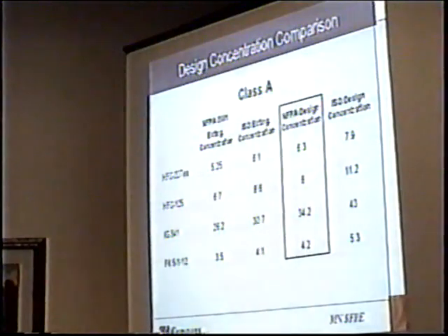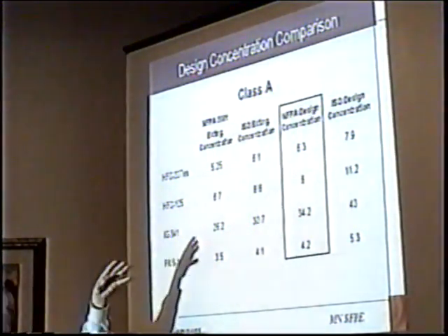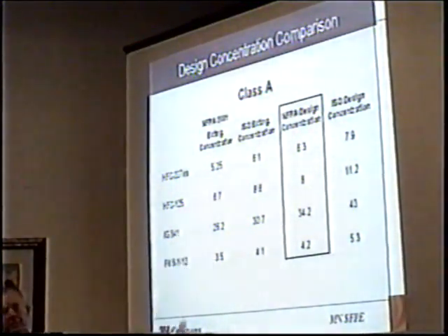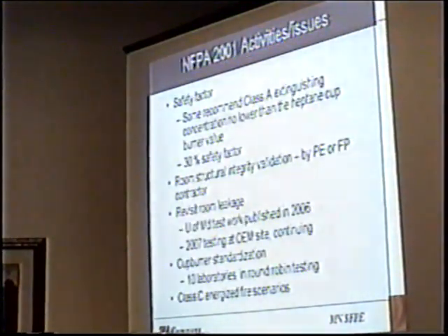What you're going to be most concerned about, what you'll see in here if you're using clean agents in the United States, is those concentrations there, as a minimum. So some of the activities that were looked at: the safety factor, what do you apply to those numbers? Some recommend the Class A extinguishing concentration be no lower than the heptane cup burner value. That went away. Some recommend a 30% safety factor. That went away actually for a second cycle now.